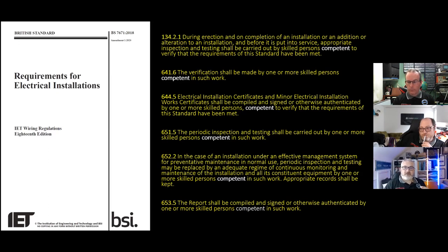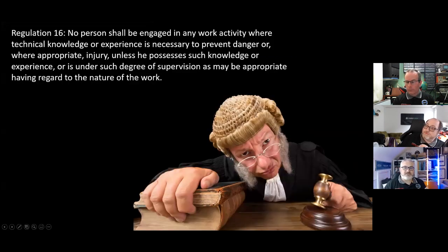So I want to kind of change this up a bit. Just what I do, Regulation 16: no person shall be engaged in any work activity where technical knowledge or experience is necessary to prevent danger. So if you know someone who's doing EICRs, it shouldn't be, because if they don't have technical knowledge or experience, they shouldn't be doing it. Again, that's like an instructed person. Or where appropriate, injury, unless he possesses knowledge and experience, or is under a degree of supervision, skilled and instructed, as may be appropriate having regard to the nature of the work.